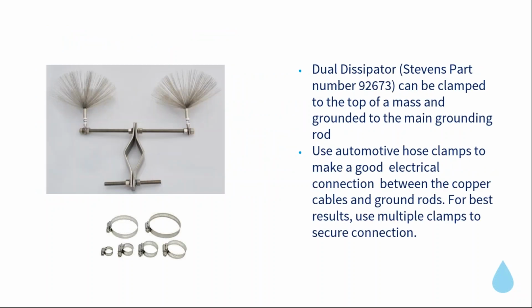So above ground, this is called a dual dissipator, and this can be clamped to the top of your meteorological station. You can get a copper cable and a grounding cable and attach it, clamp it to this, and then have this running to your grounding rod. You can use automotive hose clamps such as these, and it's also a good practice to double them up, so you can actually use two clamps to secure the connection, and also have a better electrical connection.